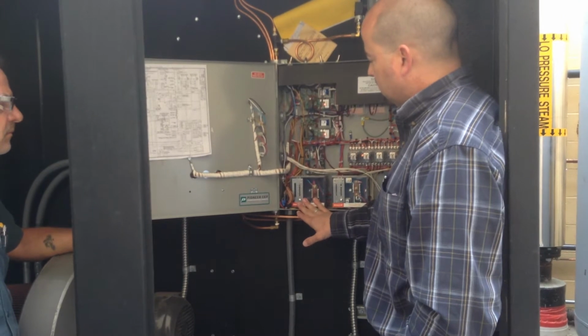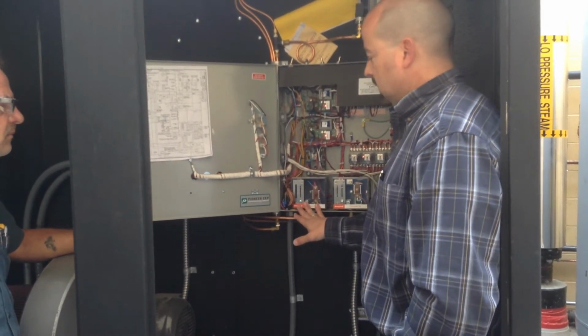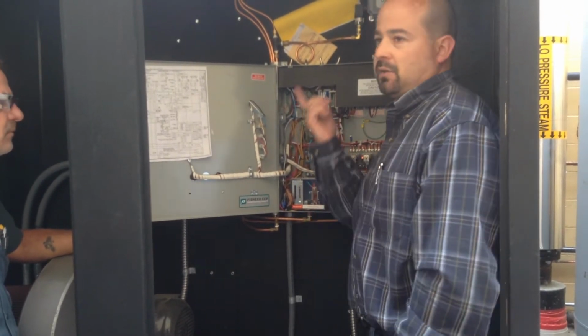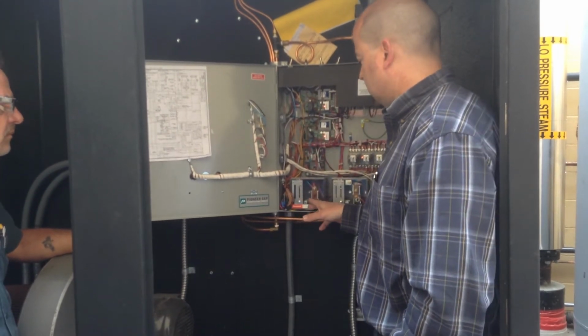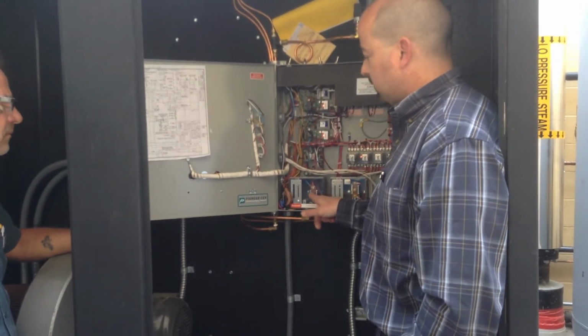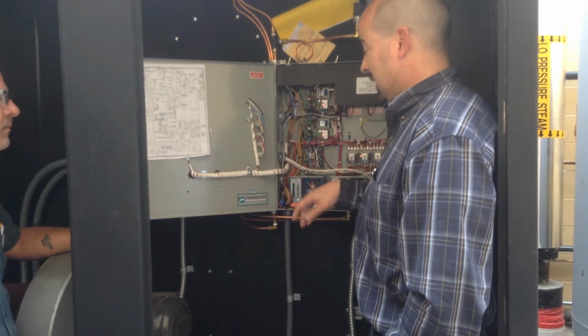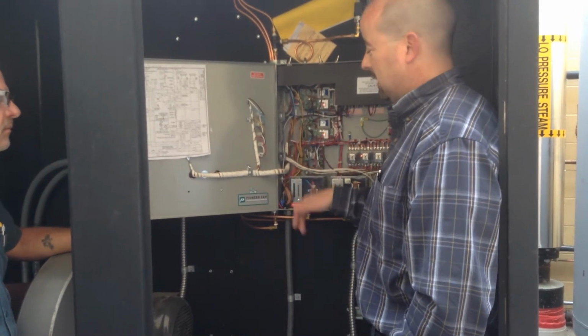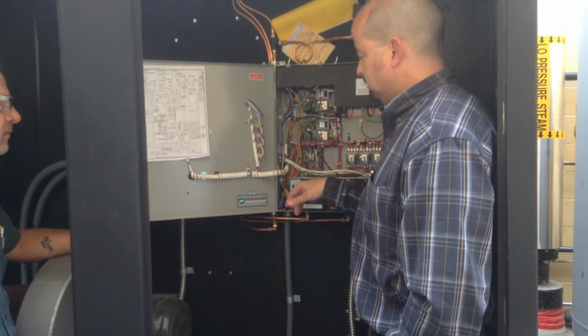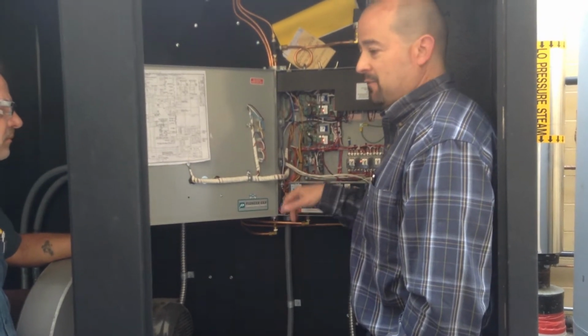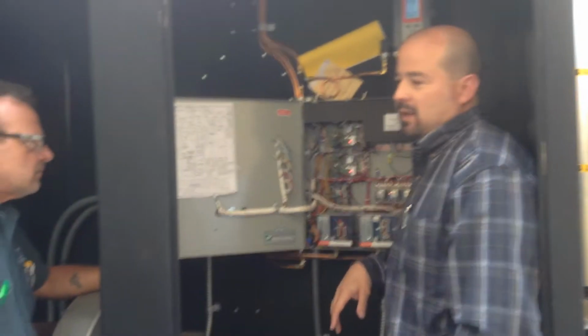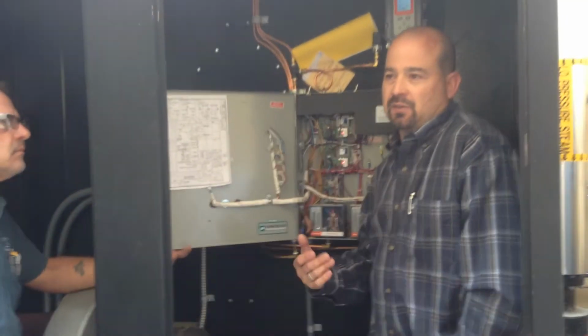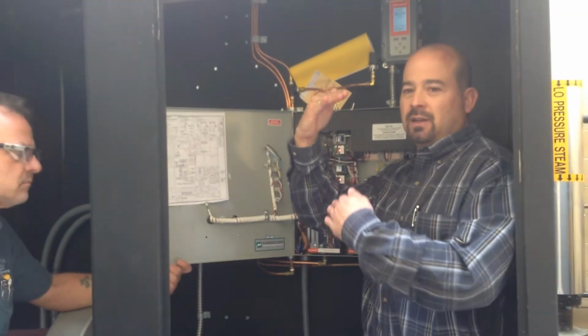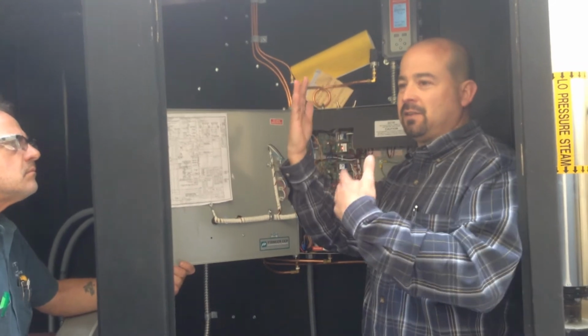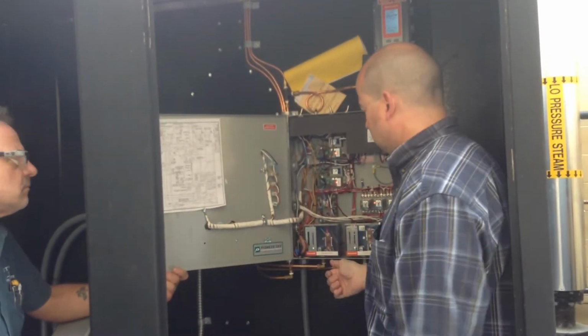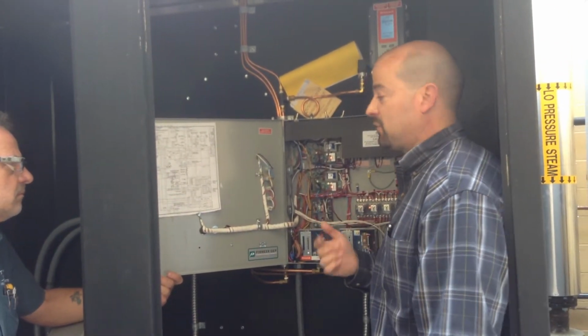This control here is a manual reset control. If the pressure were to get too high, they call it a manual reset high limit. There's a red button here that requires resetting if the pressure would ever get too high. That should never really happen, unless somebody adjusts it or it's malfunctioning. A lot of times, if somebody feeds the boiler initially the first time, it builds up a lot of air and squeezes the air pressure and fakes it out. It's not really steam, it's air pressure, so you might have to manually reset that on initial startup.